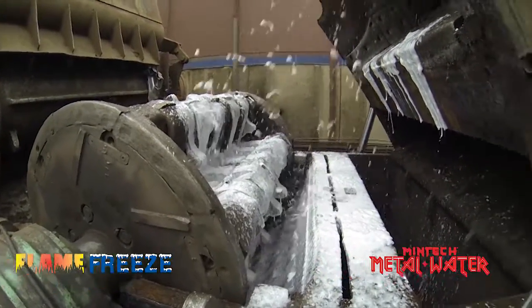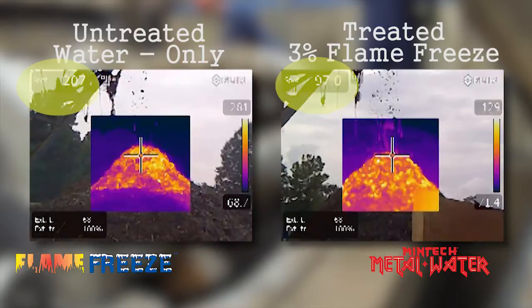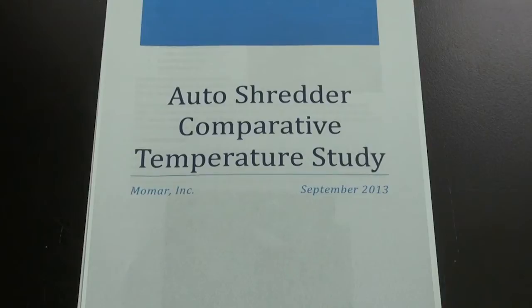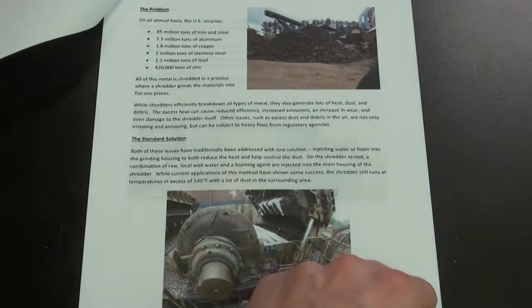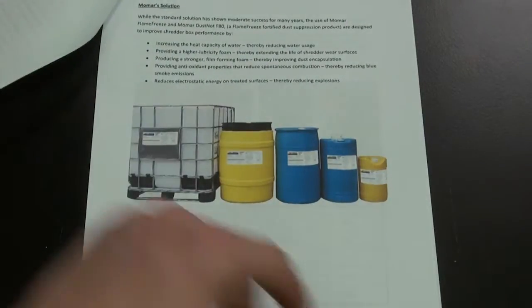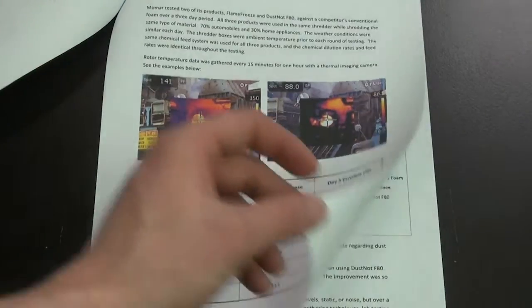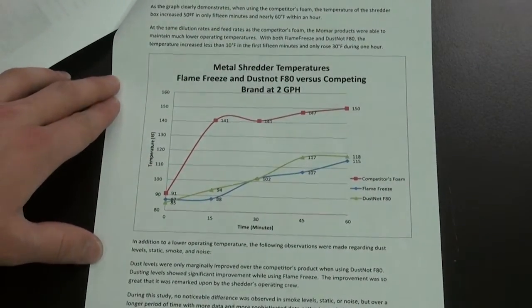The Flame Freeze fortified water spray applied during the shredding process covers more surface area on non-porous surfaces where friction is the greatest. Flame Freeze also improves water's ability to penetrate porous surfaces like fluff, where the chances of fire are the greatest. Momar has conducted extensive testing of Flame Freeze in shredder applications. During this particular study, Flame Freeze and DustNot F80 — a Mintech dust suppression foam fortified with Flame Freeze — were compared to an industry-leading brand.